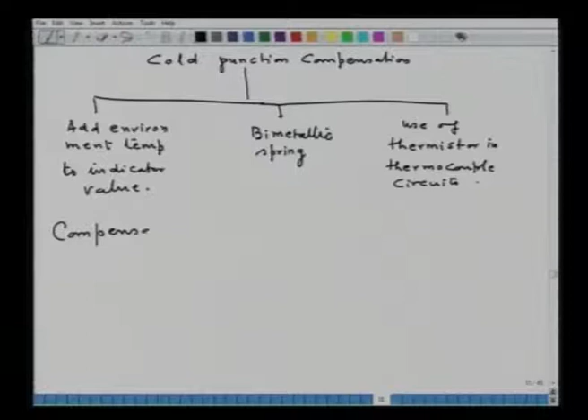Now, remember, this cold junction compensation is a very important issue. In this connection it is also important because you are connecting the thermocouple wire, and from the thermocouple wire you are going to the indicator. So, some wire you will be using outside. They are also called compensating wires. Normally these compensating wires should have the same EMF as that of the thermocouple wire, otherwise you will again record a wrong value.